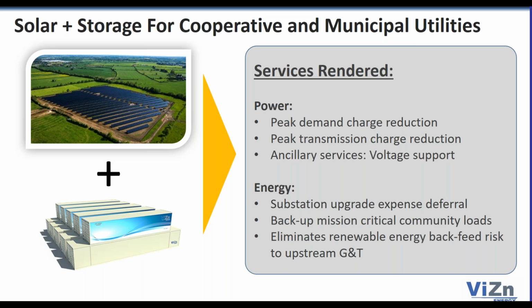A lot of these co-ops have several different substations, and it just so happens there's usually one that, due to load growth, is in trouble and would need to be upgraded with a significant capital expense in the next 5 to 10 years. By dropping in a storage system next to a solar farm at that location, the application is able to delay and defer the upgrade expense.